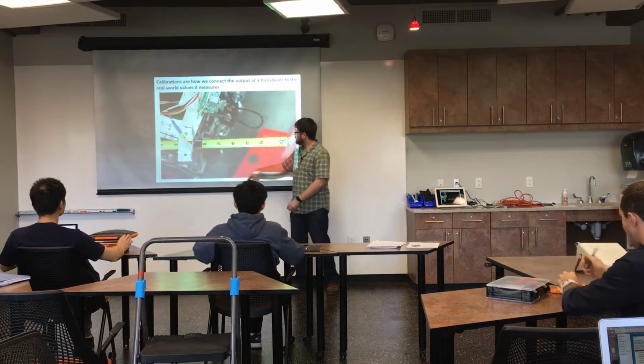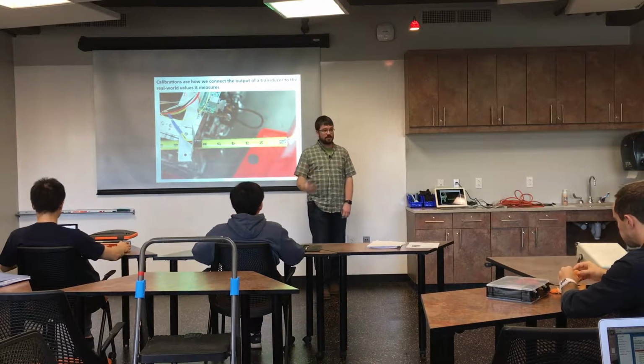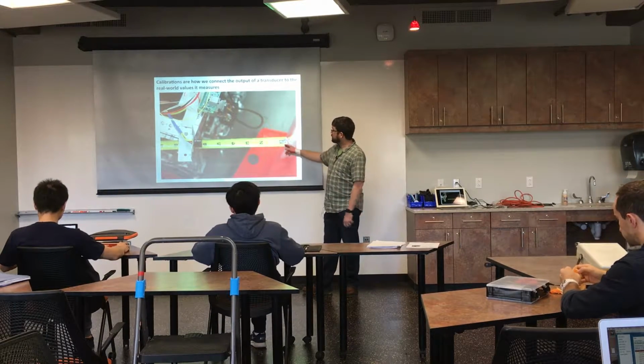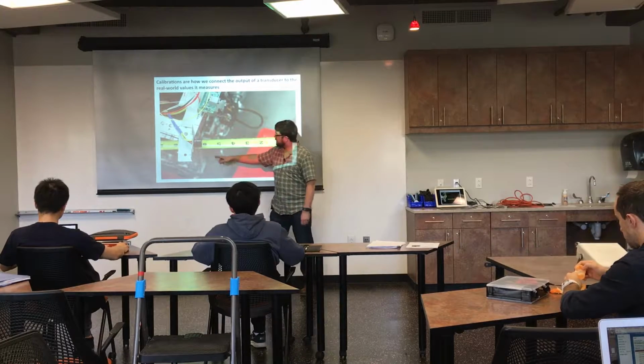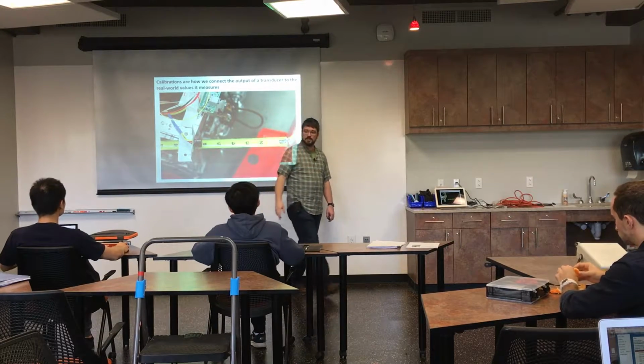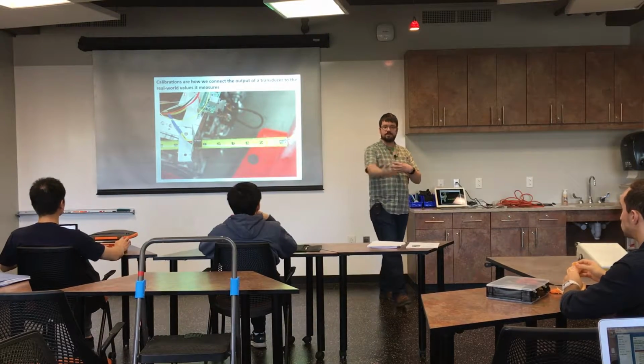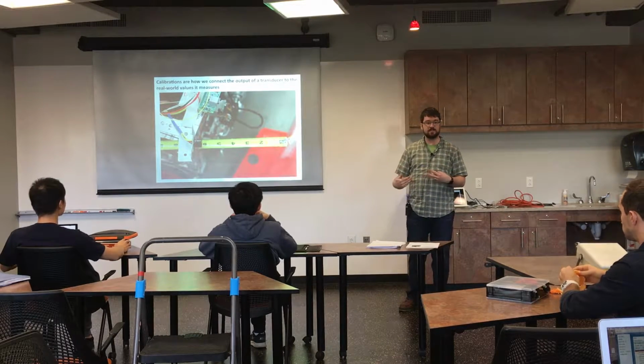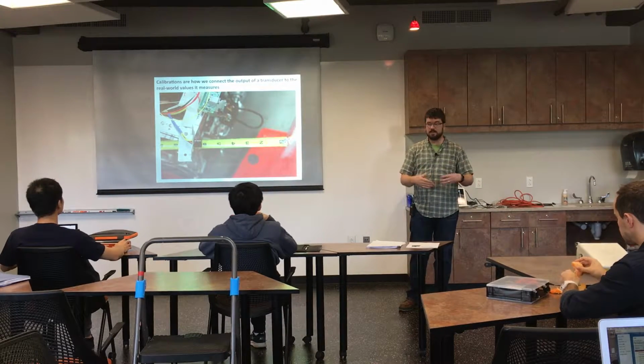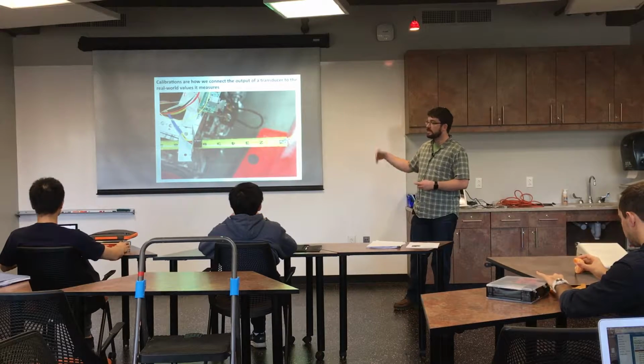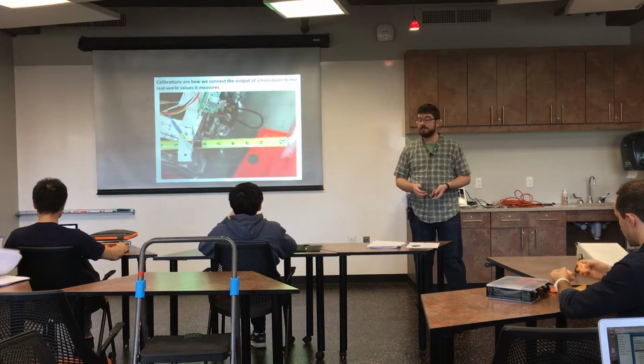So here there's a distance sensor. This is obviously not an incredibly precise calibration, but it could be good enough for their application where they have a tape measure and they have the transducer placed at 6 inches. And then they'll know that when the transducer outputs whatever value it is now, that represents 6 inches. And they would move it to, say, 7 or 8 or 10 or 12 inches, take another reading, and build up a calibration data set.